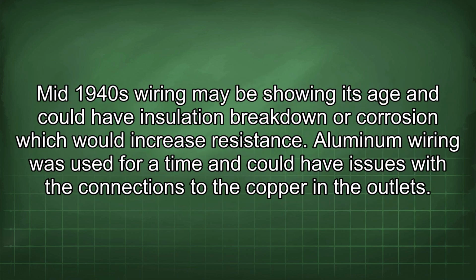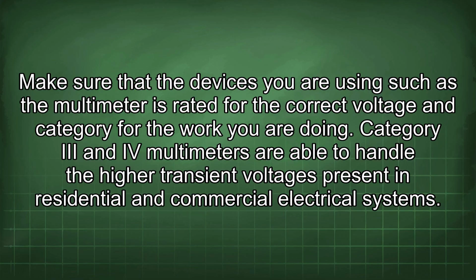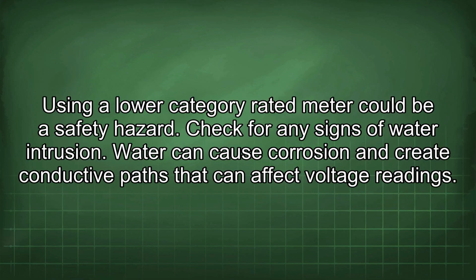Mid-1940s wiring may be showing its age and could have insulation breakdown or corrosion, which would increase resistance. Aluminum wiring was used for a time and could have issues with the connections to the copper in the outlets. Make sure that the devices you are using, such as the multimeter, are rated for the correct voltage and category for the work you are doing. Category III and Category IV multimeters are able to handle the higher transient voltages present in residential and commercial electrical systems. Using a lower category rated meter could be a safety hazard.